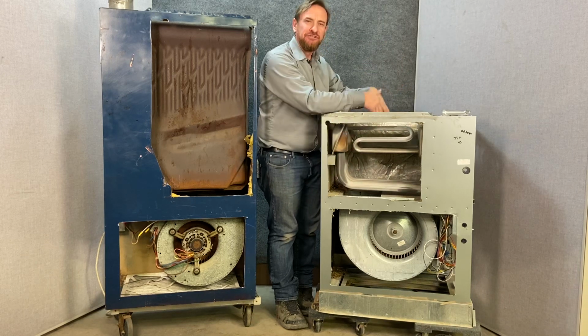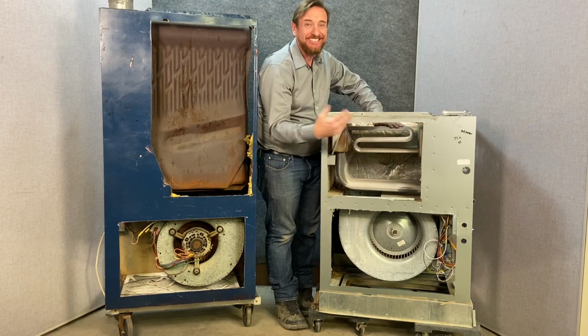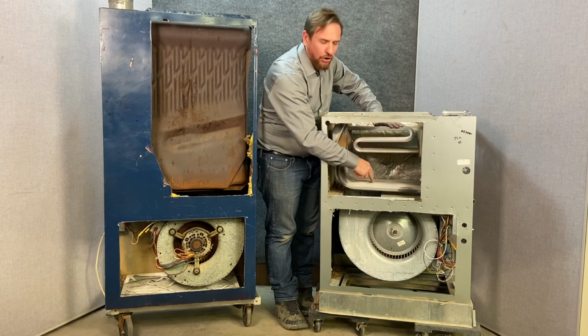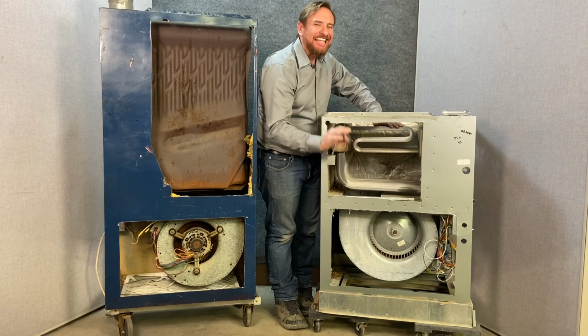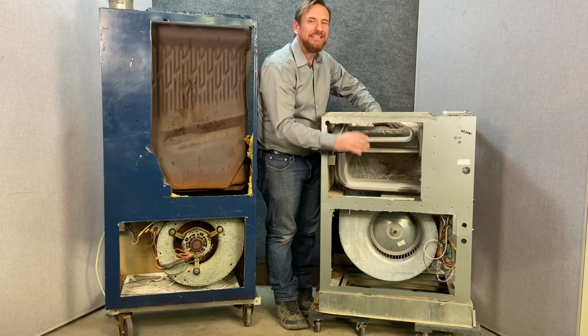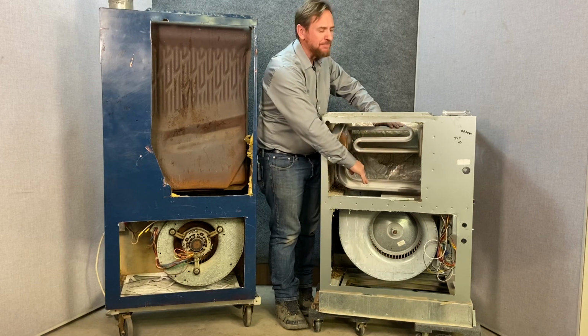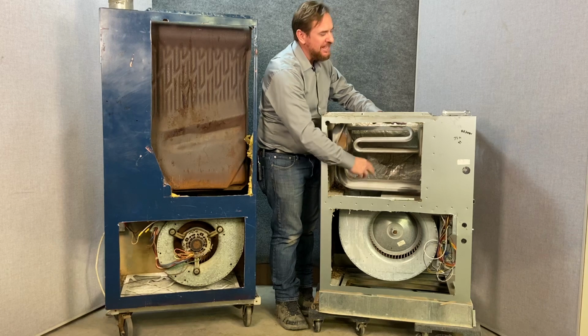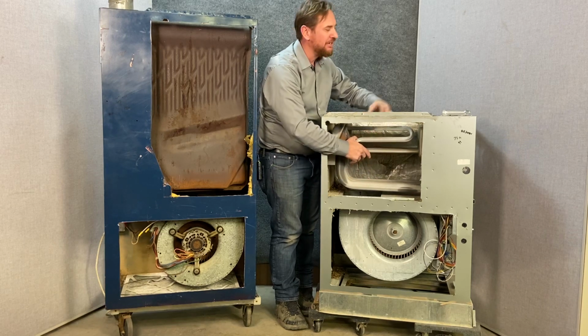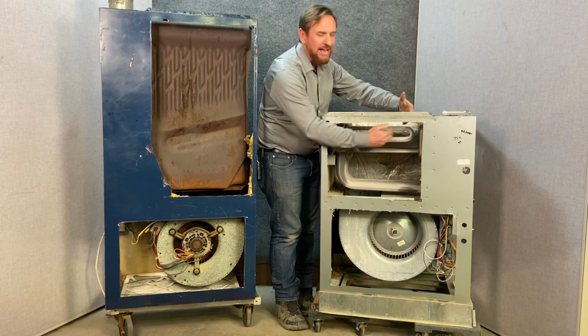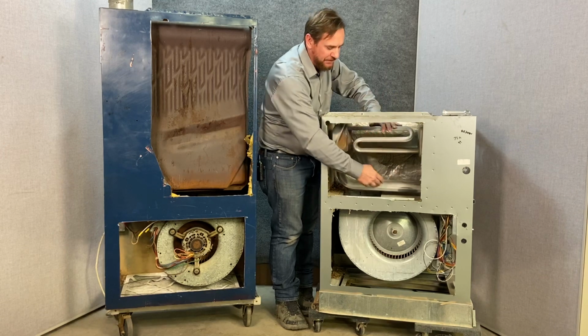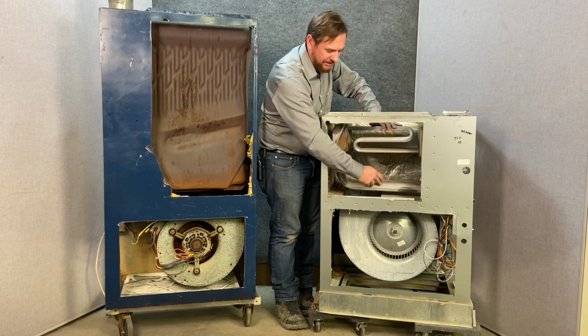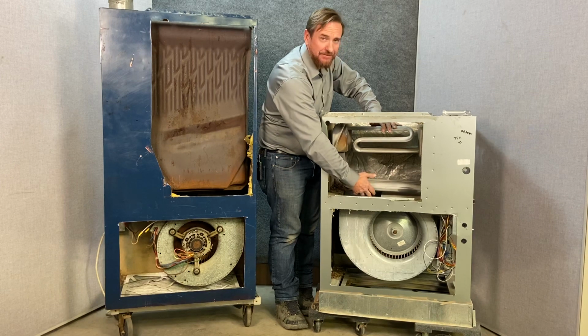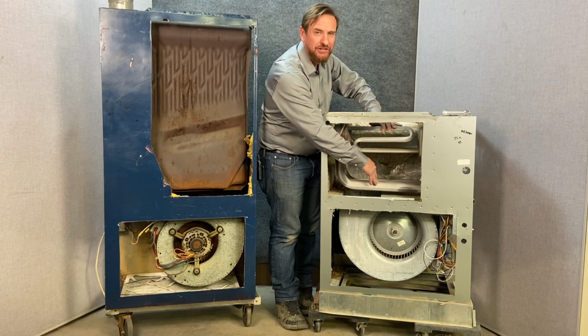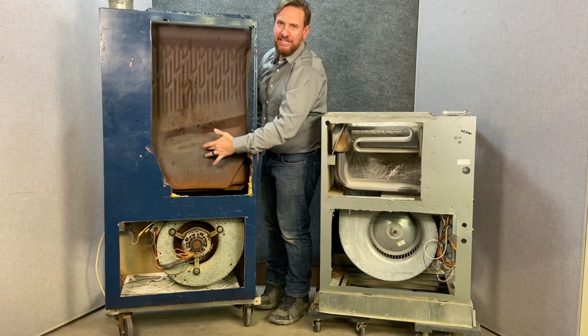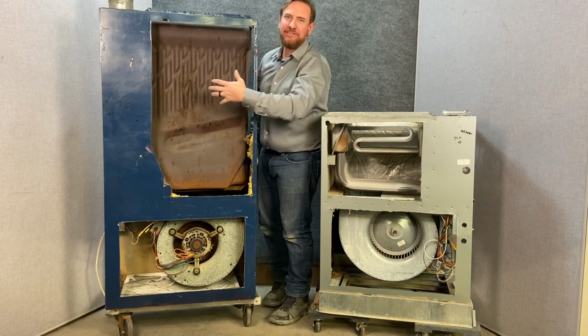If your evaporator coil is leaking water on here, it's definitely going to rust out. It's still going to be an issue. But if you had a hole in this heat exchanger, it's less likely, still possible, but less likely to immediately poison the customer. Because if you have a hole in this heat exchanger, this whole heat exchanger is under negative pressure. This fan is pulling a draft through it. The idea is if you get a small hole in here, the air from the house would actually go into the heat exchanger, whereas with this one, a hole in the heat exchanger would be pulling gases out into the house.